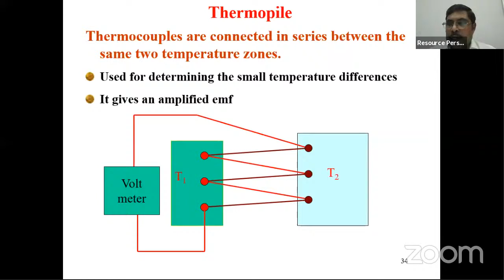Basically, a thermopile is a combination of the same kind of thermocouple. Here you need to connect thermocouples of either T or K type in series. Okay, you see here, in this particular figure I made 3 junctions in T2 and 3 junctions in T1. Therefore, whatever output comes out of this net circuit will be 3 times the actual output. So here the voltage is getting multiplied, and therefore you can minimize the error. Basically, this thermopile circuit is used in the IR thermometer. Okay, I will explain that in a later slide.